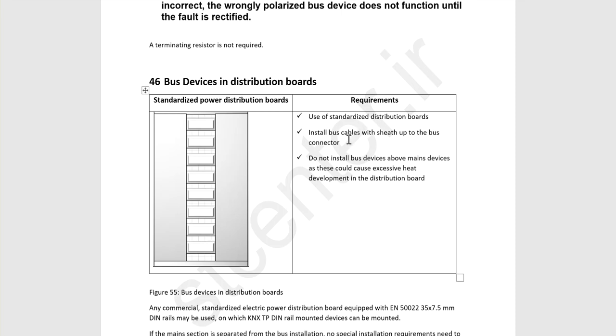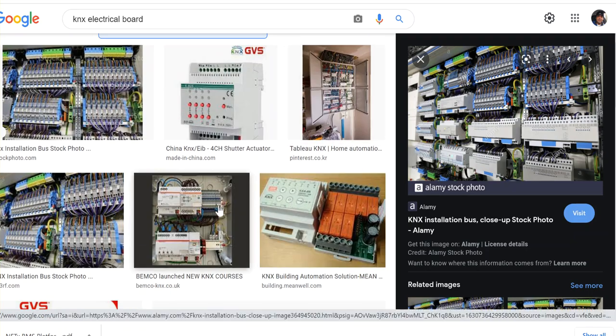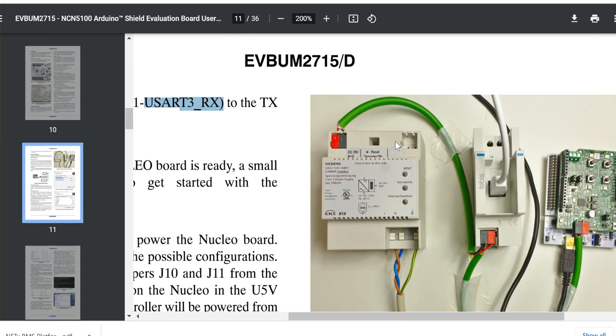Then we should install bus cables with the sheath up to the bus connector. What does it mean? It means the green cover of the wiring should continue to the KNX connector. You can see in the picture in this example the green cable comes to the KNX connector. So this is true. It means we cannot connect devices without the green cable in the distribution board.